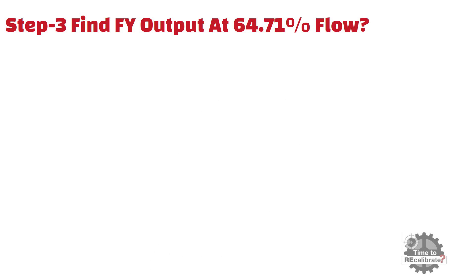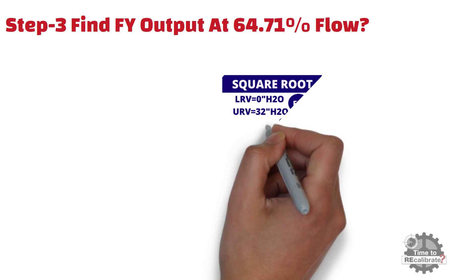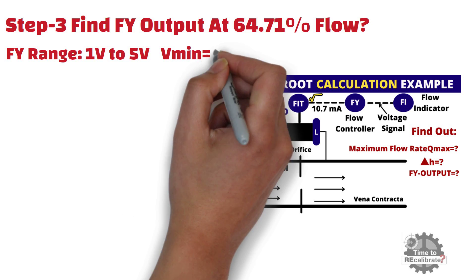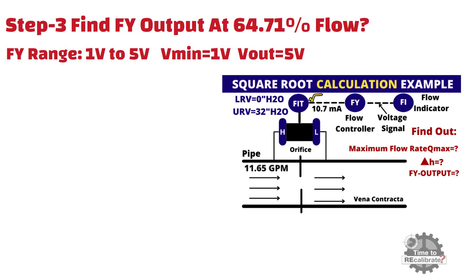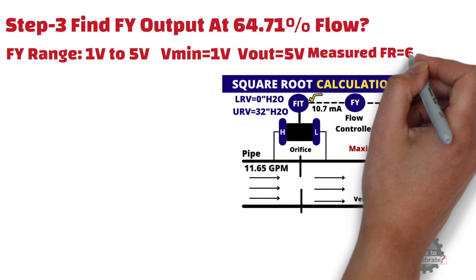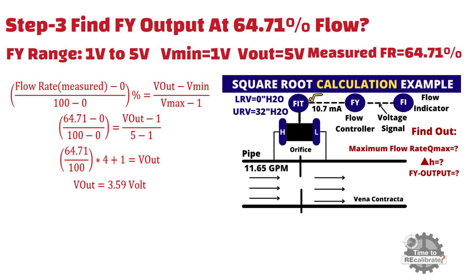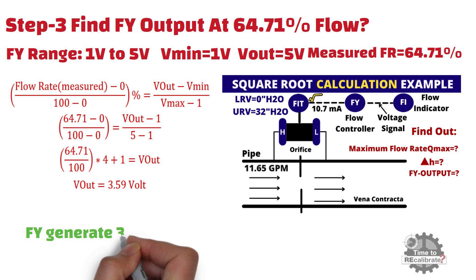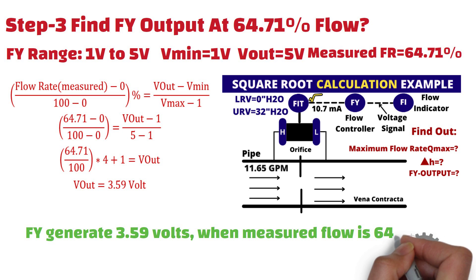Step number 3: Find the flow controller output when measured flow rate is 64.71%. In this example, the flow controller range is 1 to 5 volts, meaning minimum range is 1 volt and maximum range is 5 volts, and measured flow rate is 64.71%. Put all these values into the standard equation and do the simple math. You will get 3.59 volts — in other words, the flow controller will generate 3.59 volts when measured flow rate is 64.71%.